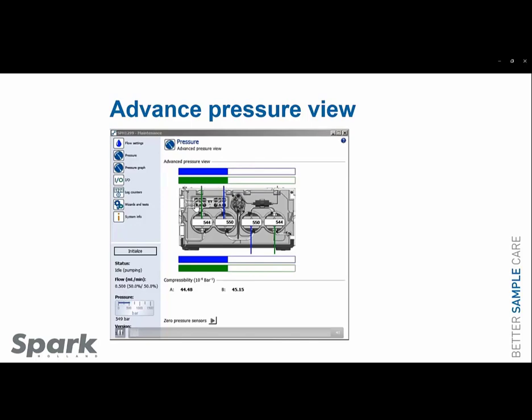During the loading stroke of the primary pump head, the green bar will drop. The system pressure is stable. You will also notice that there's a compressibility calculated in here. Because the values of compressibility are almost equal, we can assume that the mobile phase inside both pumps is similar. The pump is running 50% A, 50% B, at a flow of 500 microliters per minute.